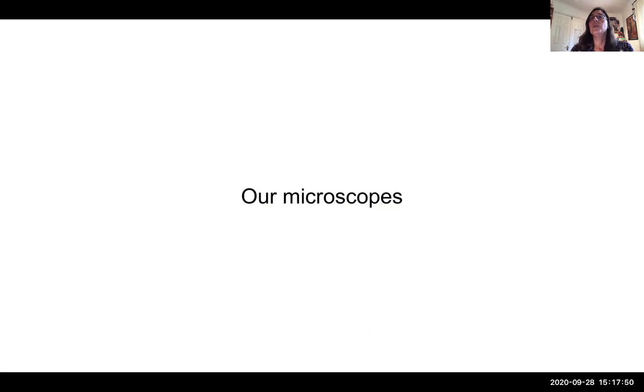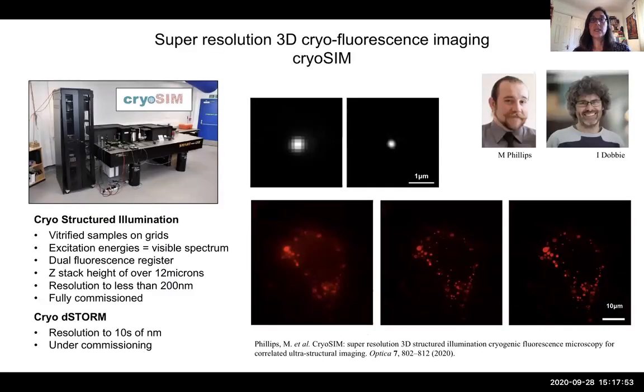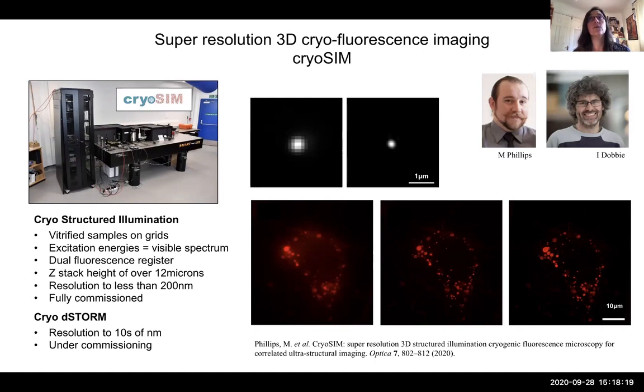Now I'll start with the fluorescence imaging, specifically the cryoSIM — that's structured illumination microscopy. It looks into vitrified samples on grids and has a wide spectrum of illumination. We can register two fluorescence signals at the same time, and we look through cells with a Z-stack of about 12 microns or more — really thick for this type of sample. With a resolution of better than 200 nanometers, this is fully commissioned and easily accessible. The cryo-dSTORM functionality is there but still under development, so slightly higher risk.